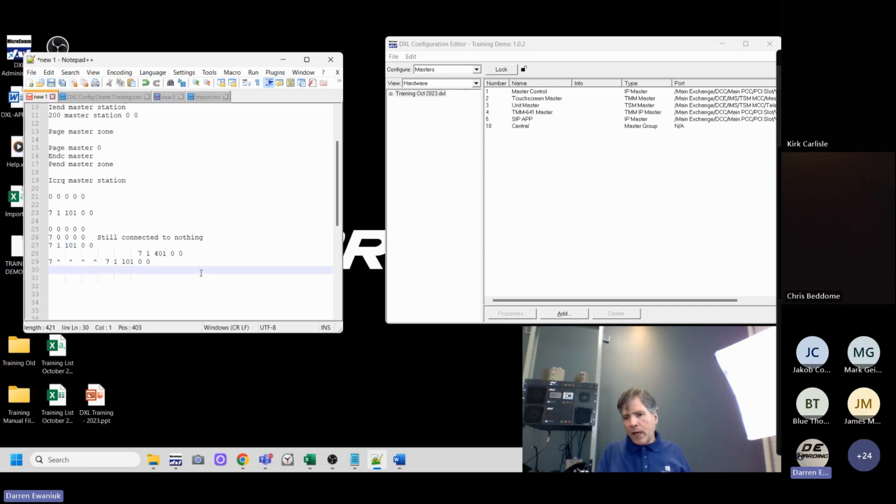What typically happens is that you set a scanning rate. You might say 5 times a second or 10 times a second as your polling rate. It's going to read all the registers from the DXL system, copy them to a local copy, and then you look to see if anything has changed.